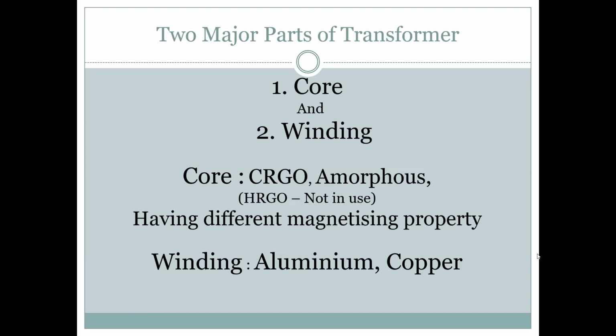It is not yet that successful, I must say, for industrial purpose use, but still there are quite a lot of uses going on. Earlier there was CRGO, and there is one more steel, HRGO, which is not used for transformers. What steel do we use for motors? That is CRNO, cold rolled non-oriented, non-grain oriented. You don't need that particular grain formation, that metallurgy requirement is not there in the motors or fans or whatever we are using here. That is CRNO steel.